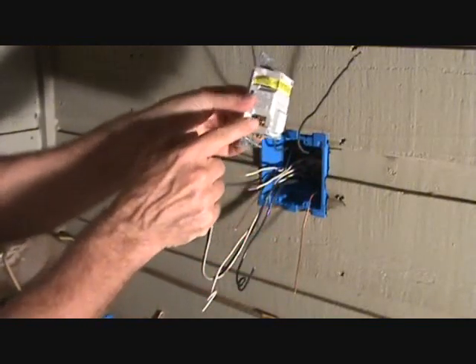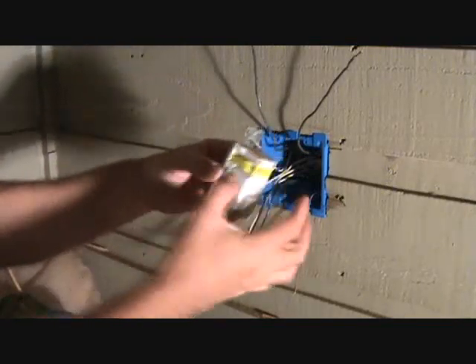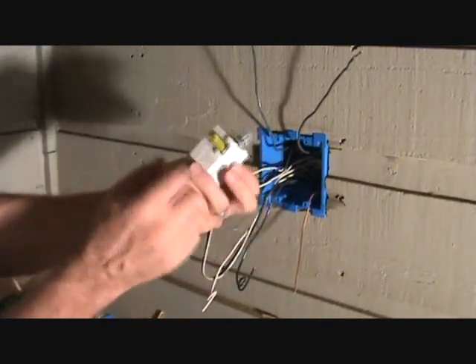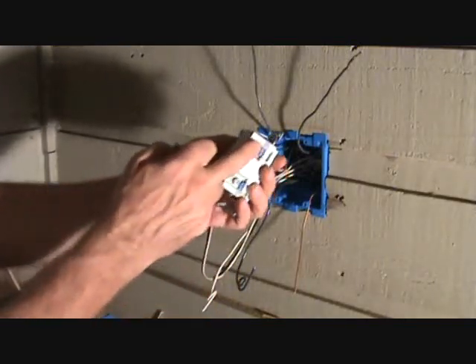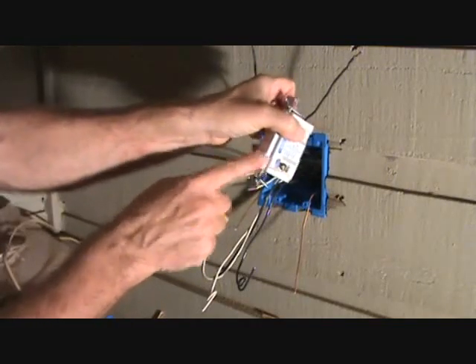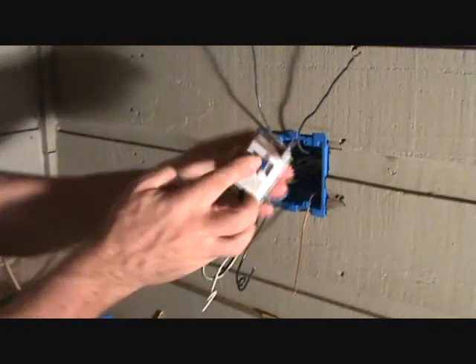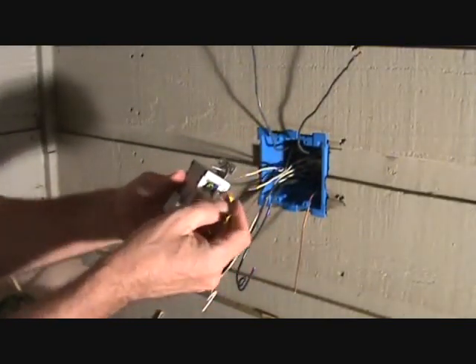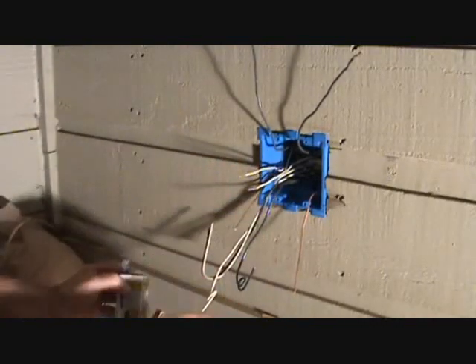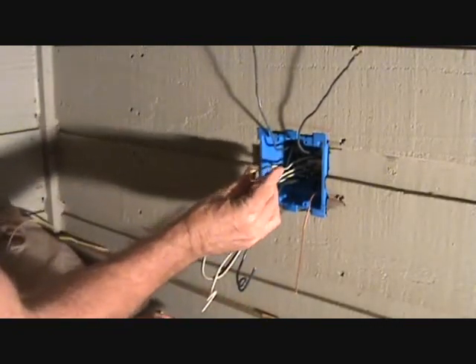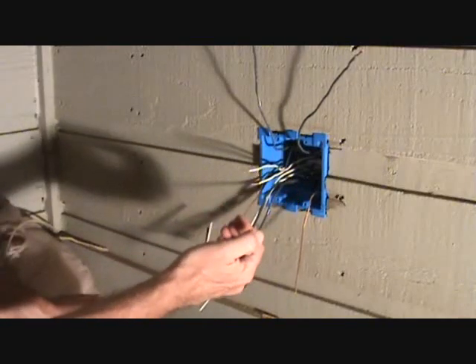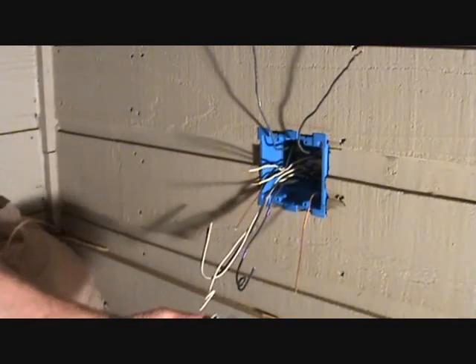So there's a proper way. The power goes in from here. If you want to connect to any other wires coming out of this box, you've got it attached to these top screws. See, there's a screw there, and there's a screw there. Here's where we're going to attach the main power coming into the box. It's to the bottom here. And then going out of this box is this top, this screw, and this screw. So I'm just going to put that tape on there so I don't get mixed up. So that's why we have to connect just these two white wires together that were original. Usually you attach all the wires, all the white wires together, and then come out with some pigtails, but we can't do that. And I just explained why.